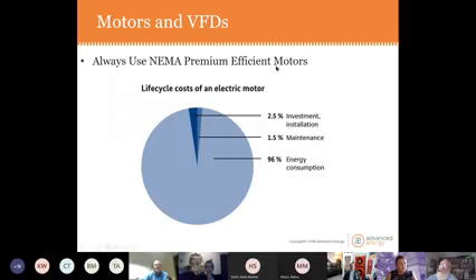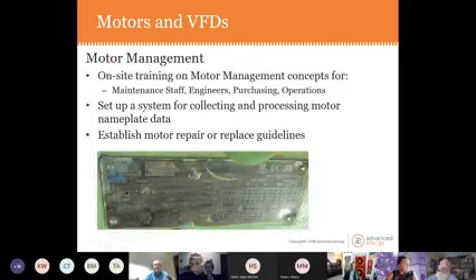Always use NEMA premium efficient motors. If you look at the 20-year life of a motor, 96% of the cost of that 20-year lifetime of that motor is the energy, the electricity it consumes. So if you can convince purchasing to spend $500 extra to buy that 96% efficient motor instead of that 94% efficient motor, that's cheaper, but over that lifetime, that 2% difference in the efficiency of that motor, you're going to pay that back 100 times over. So use NEMA premium efficient motors always.